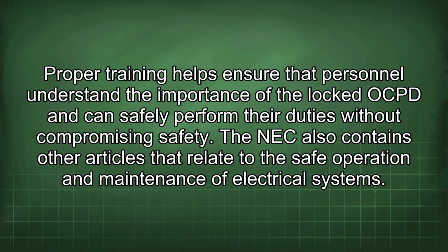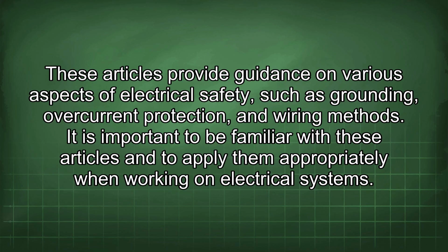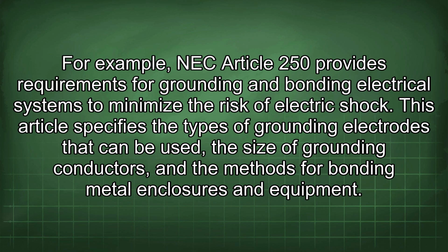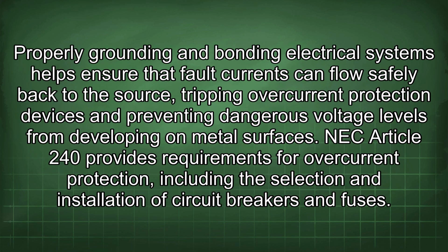The NEC also contains other articles that relate to the safe operation and maintenance of electrical systems. These articles provide guidance on various aspects of electrical safety, such as grounding, overcurrent protection, and wiring methods. It is important to be familiar with these articles and to apply them appropriately when working on electrical systems. For example, NEC Article 250 provides requirements for grounding and bonding electrical systems to minimize the risk of electric shock. This article specifies the types of grounding electrodes that can be used, the size of grounding conductors, and the methods for bonding metal enclosures and equipment. Properly grounding and bonding electrical systems helps ensure that fault currents can flow safely back to the source, tripping overcurrent protection devices and preventing dangerous voltage levels from developing on metal surfaces.